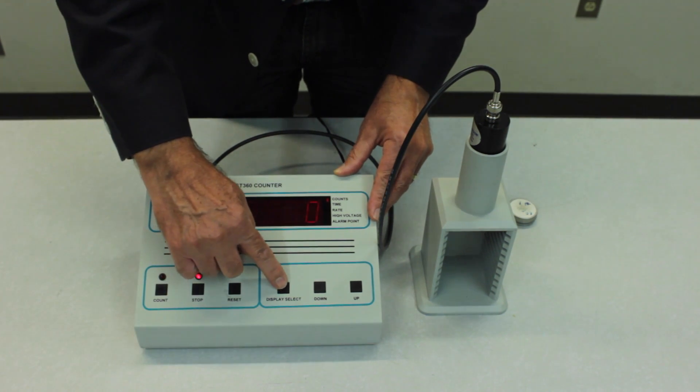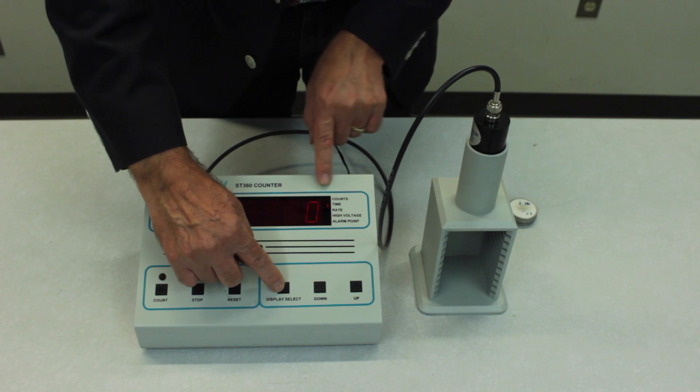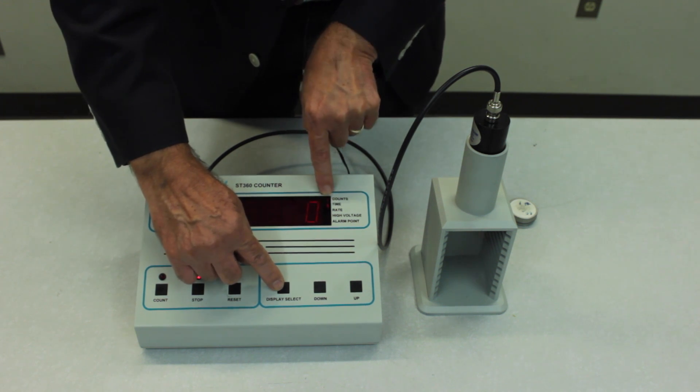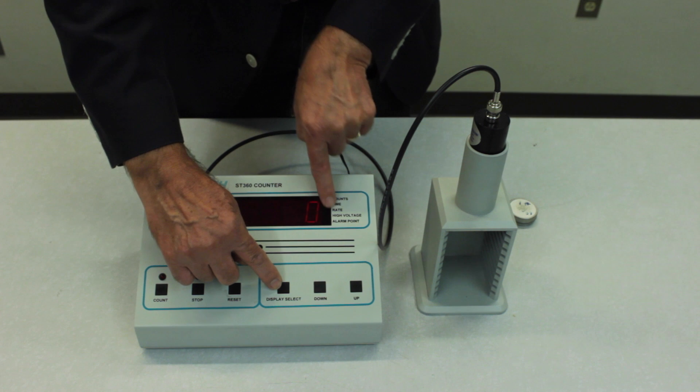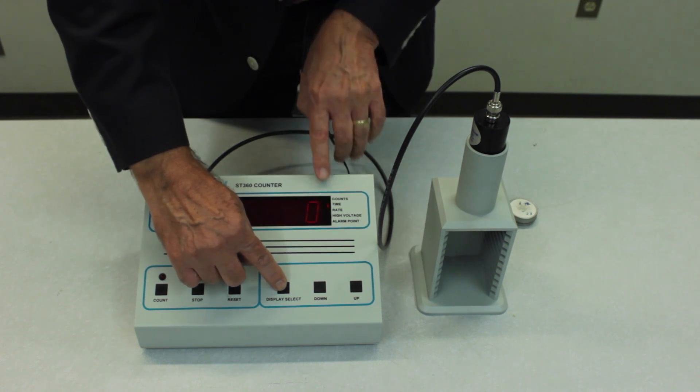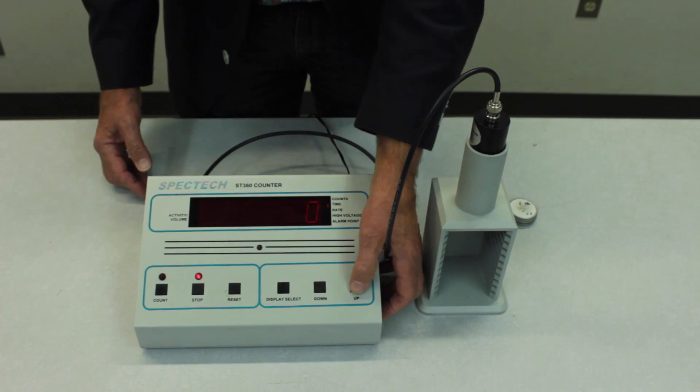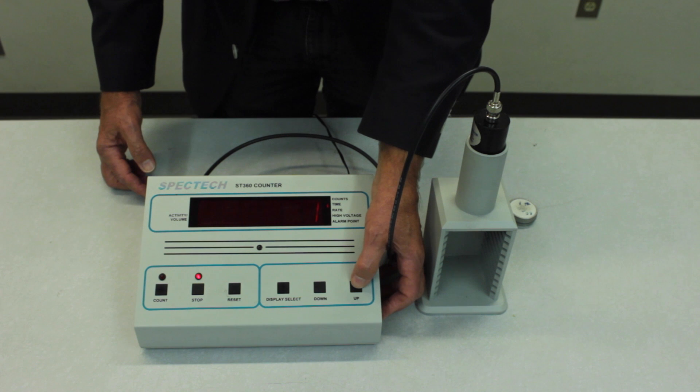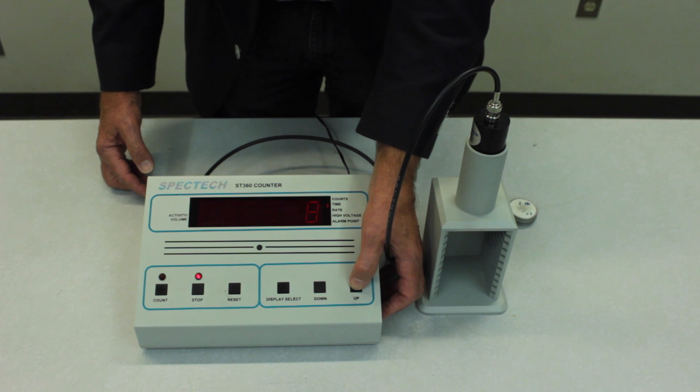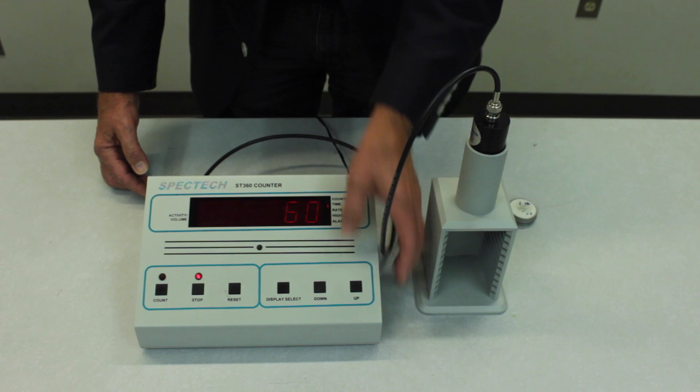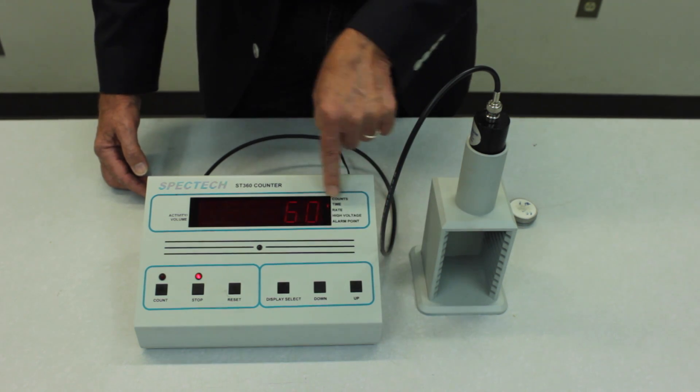So you choose the display select button and that moves the cursor on the right side of the window to these various functions. So let's start by setting the time and we'll just press the up button to increase the time. This goes in increments of one second at first up to ten seconds, and then it goes in increments of ten seconds. Let's set this at sixty seconds. So we'll do a number of counts per minute. So set the time interval for sixty seconds.